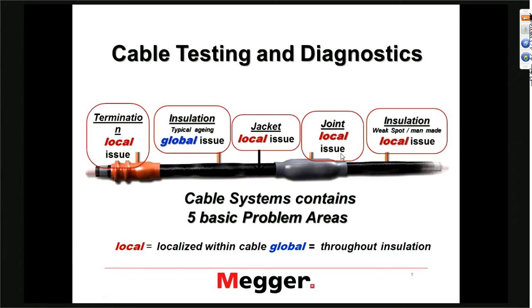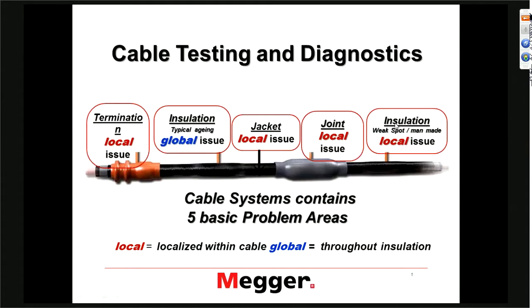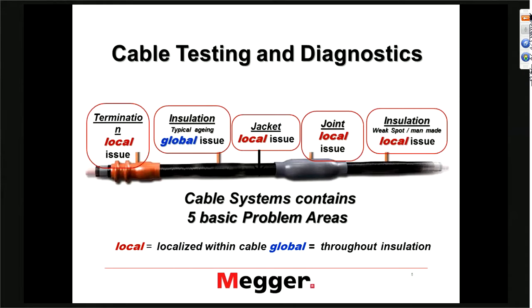We have the joints or splices, which are also of local nature. Most of the time when we deal with splice issues, they are related to workmanship. On the right side, you see insulation again. The insulation could also have some local issues, but they are typically induced — opposite to the aging we talked about before. If we have local issues to the insulation, they are typically a result of the installation process. To summarize: local issues are localized within the cable, and global issues are throughout the insulation.